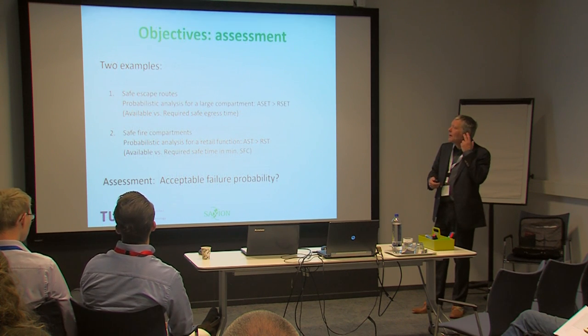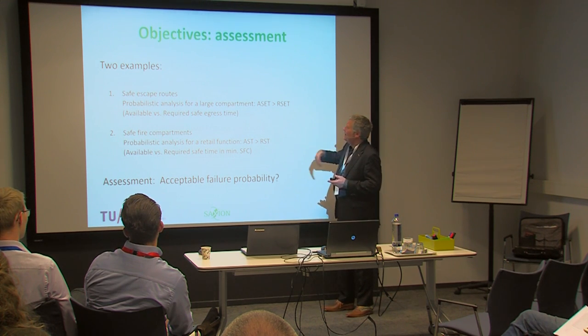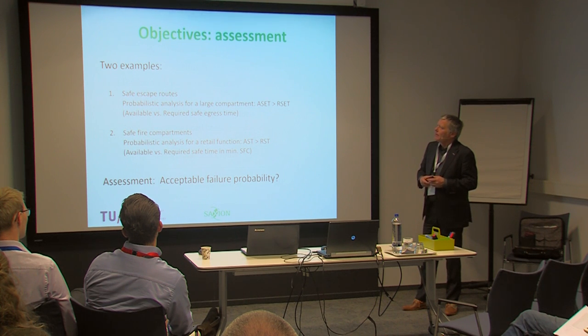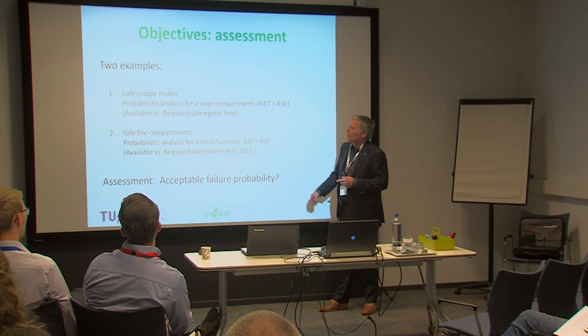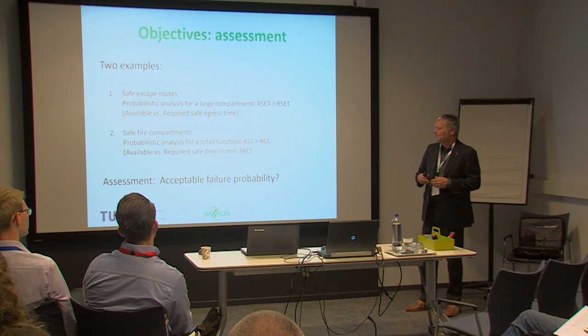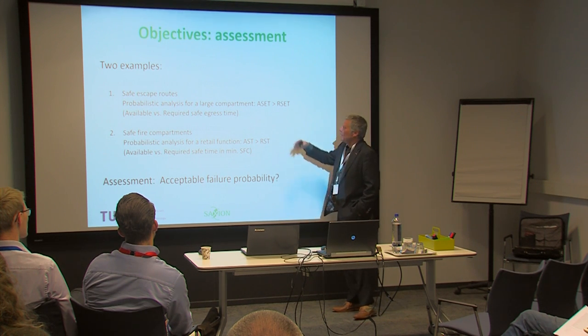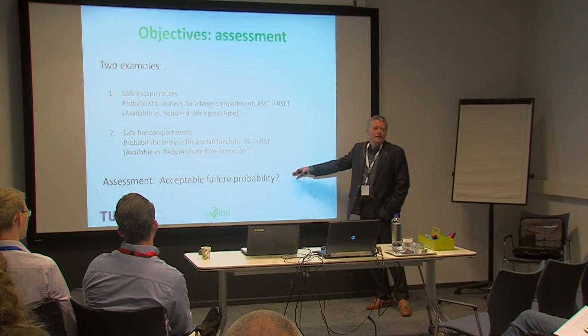I have two examples. We are used to comparing ASET versus RSET — available safe egress time versus required safe egress time — for personal safety. But you can do the same for basically any other risk subsystem. When it comes to compartmentation and fire compartments, we can also think in available safe time and required safe time, but then it's not a safe egress time — it's a level of reliability. The assessment is: what interval do we need to have an acceptable failure probability? That's a difficult discussion because we can't find these answers in building codes.